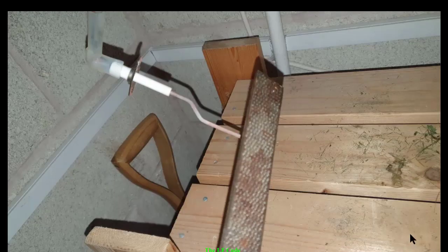Again, with this electrode you can give it a clean. I suggest you do that because this can also give that fault, because what can happen along the circumference of the flame detection electrode, you can get a lot of pitting building up, and that can cause an insulation and stop it actually sensing the flame and give the LF code.